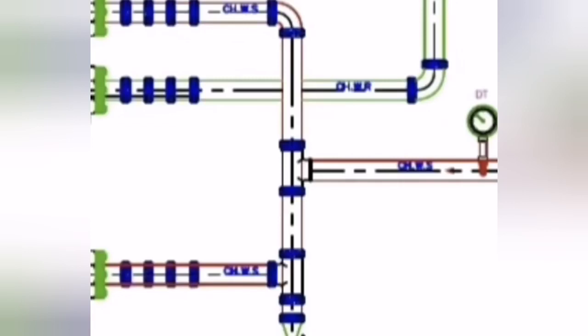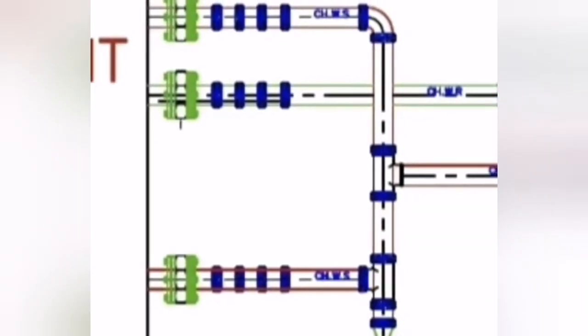Whenever you want to maintain the AHU, during maintenance you will change the chilled water and replace it with fresh water. So you need this drain valve in the pipe, which is very necessary and very important. After this, here you can see the drain line. The drain line is used to drain the vapors or the water that condenses on the cooling coil inside the AHU.